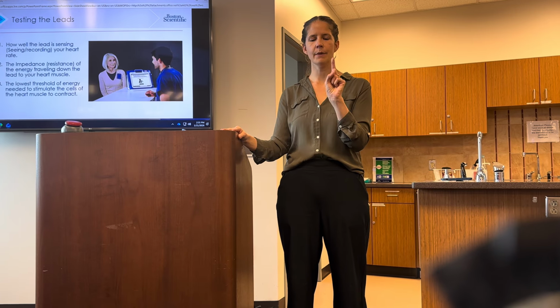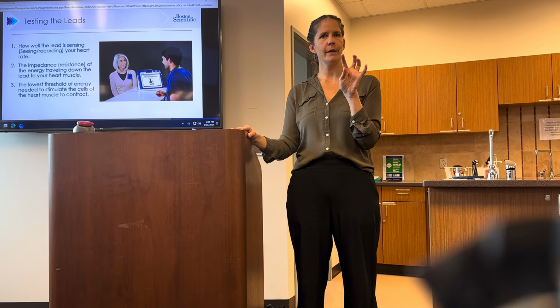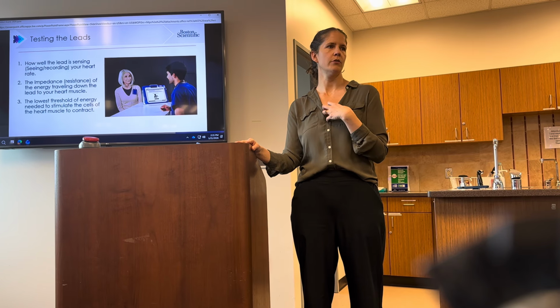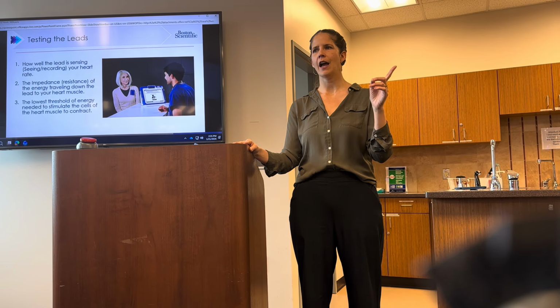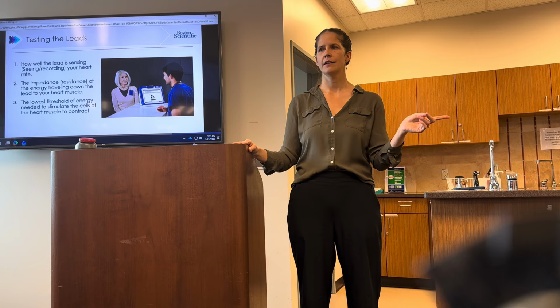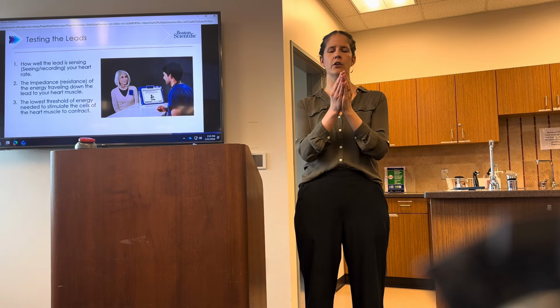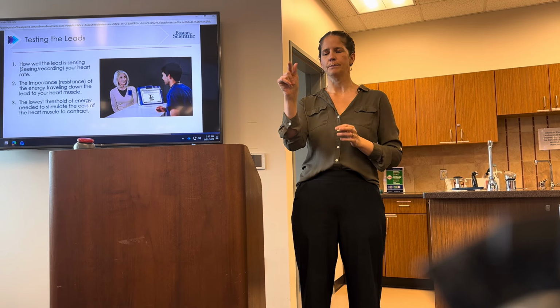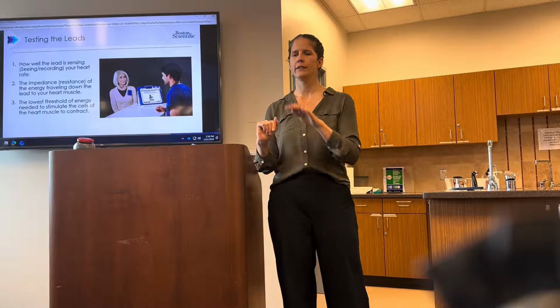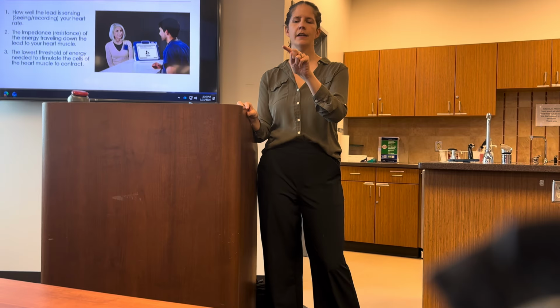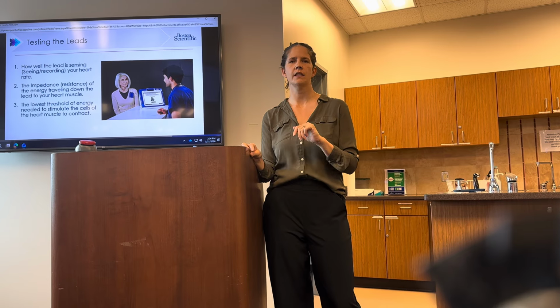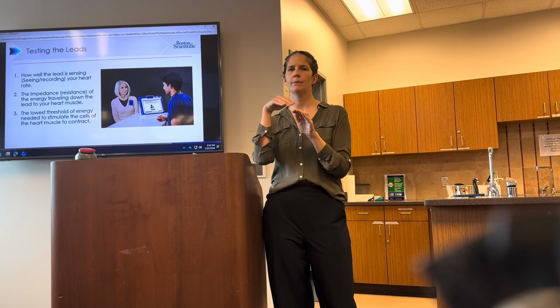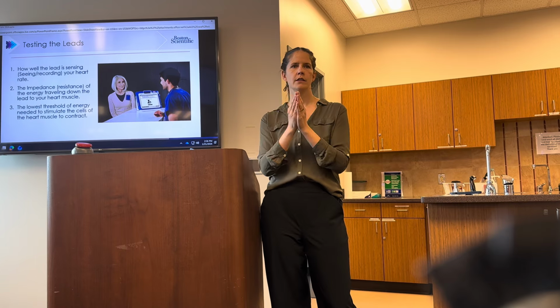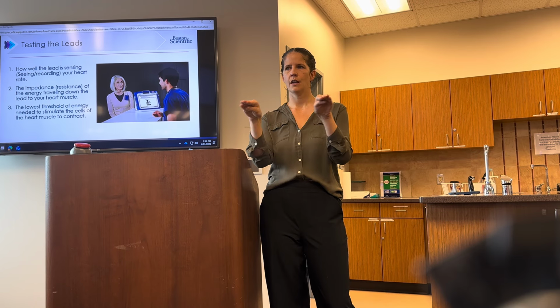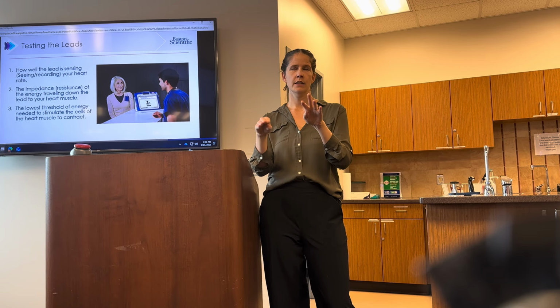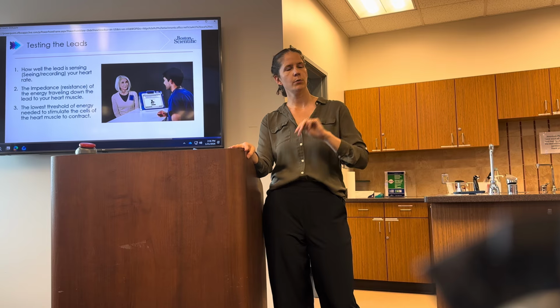What I'm doing is I'm forcing the pacemaker to pace your heart above your own heart rate so I'm in control. And then I'm decrementing down how much energy it takes this pacemaker to make the cells of your heart contract. So, say it's 1 volt and I go to 0.9 volts, all of a sudden your heart doesn't like the signal and won't squeeze. I go back up to 1 volt and it will squeeze. So that, we call that the threshold, how much energy is needed. So, those 3 tests we're always looking at.